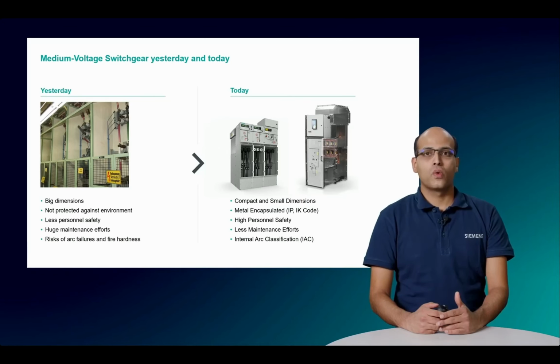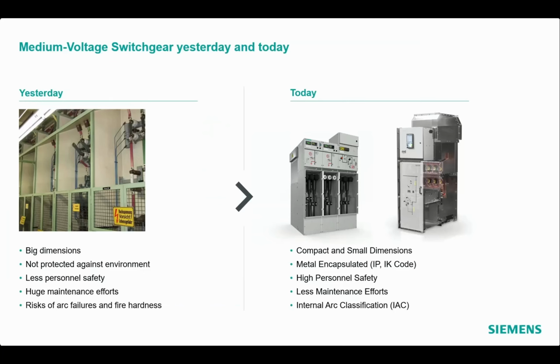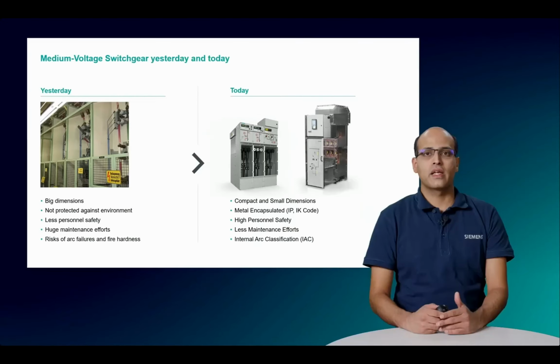Looking at the picture, one can say that the switchgears of the past require extensive maintenance efforts to keep them in good working condition, to avoid frequent repairs and downtimes. Meanwhile, the current switchgears require less maintenance efforts. Lastly, the switchgears of the past have high risks coming from arc failures and less fire hardness. On the contrary, modern-day switchgears are tested according to the internal arc classification defined in the norms, setting specific safety standards.